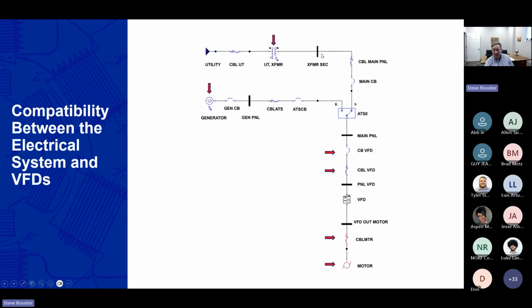Dry type transformers are going to be the most challenged. I remember doing a big retrofit project with a power plant where we converted over a dozen large cooling tower motors, and they had a dry type transformer feeding that particular cooling tower, for which we had to develop some special harmonic mitigating reactors for each of the drives that reduce the distortion and the stresses on that transformer, which would have overheated based on the numbers that we were reading of the voltage harmonic rise. But the utility transformers, while a little bit more tolerant, especially when they're oil filled, one of the first concerns is, is there going to be an overload in the transformer? And the utility's ultimate concern is when it gets back into the grid, are other customers going to be affected by that? And I'll get into what they've done about that and where their concerns are.